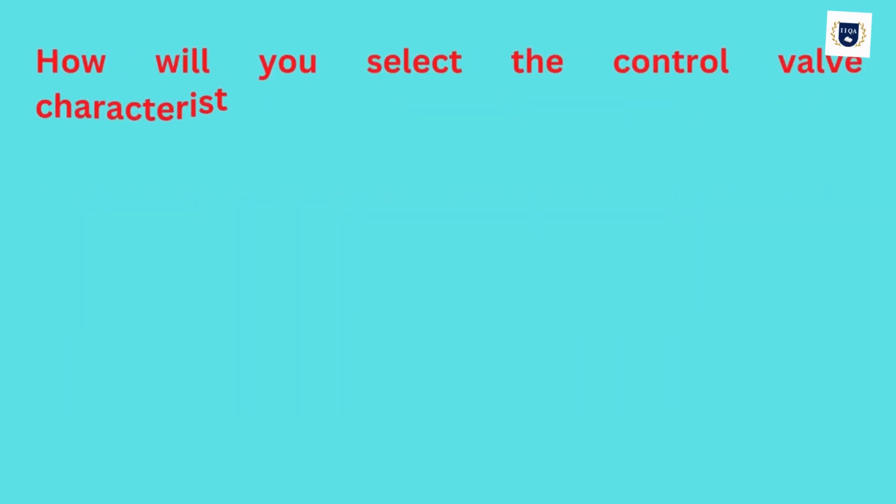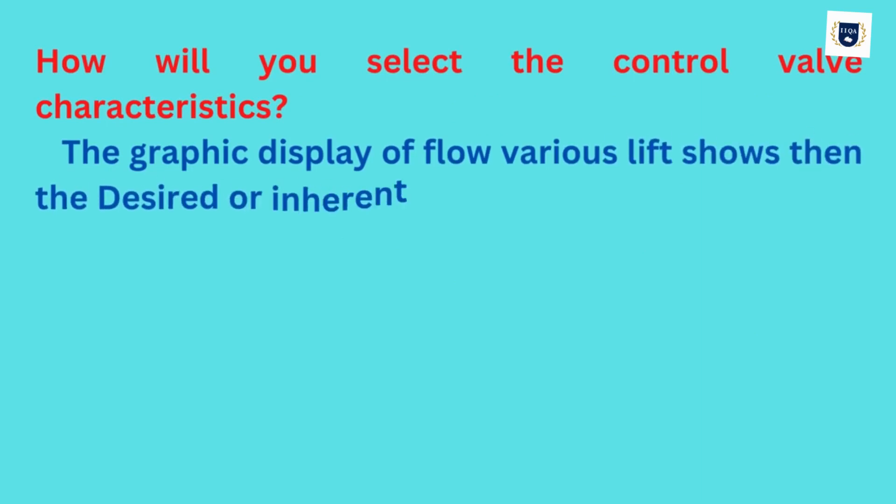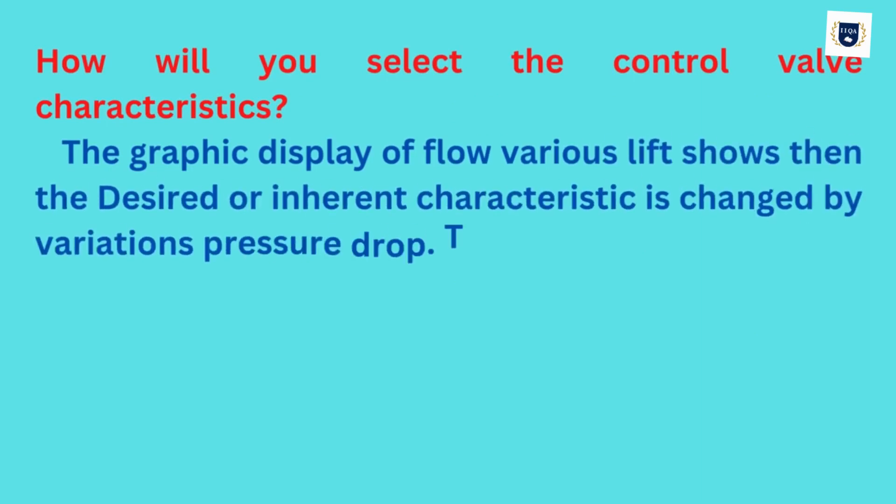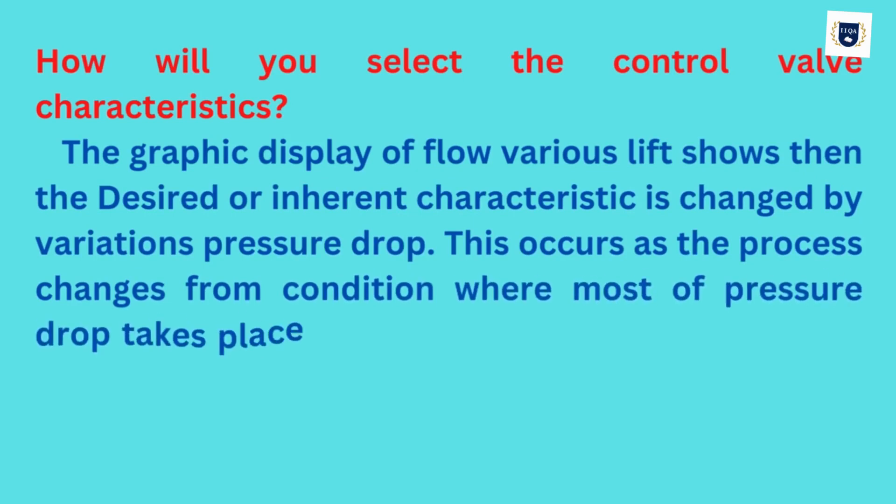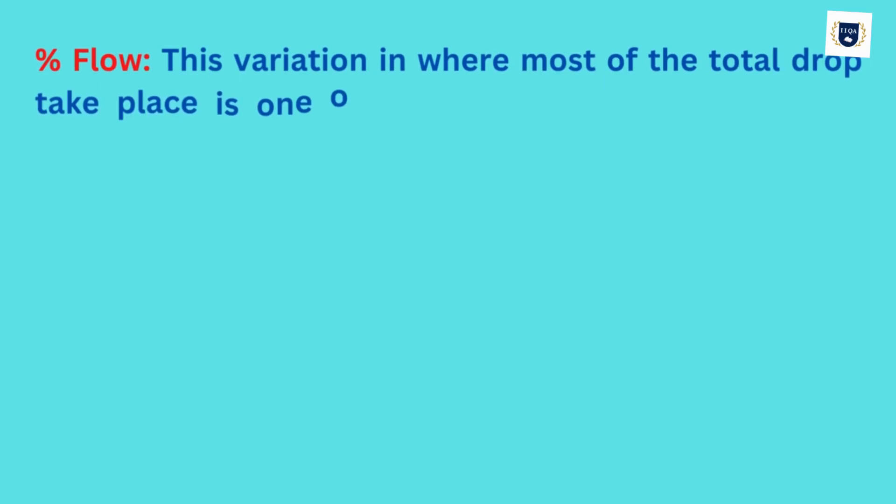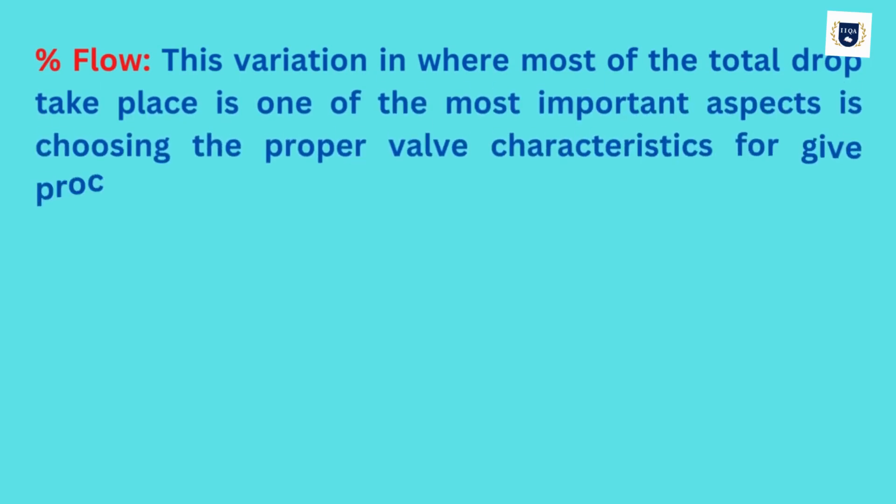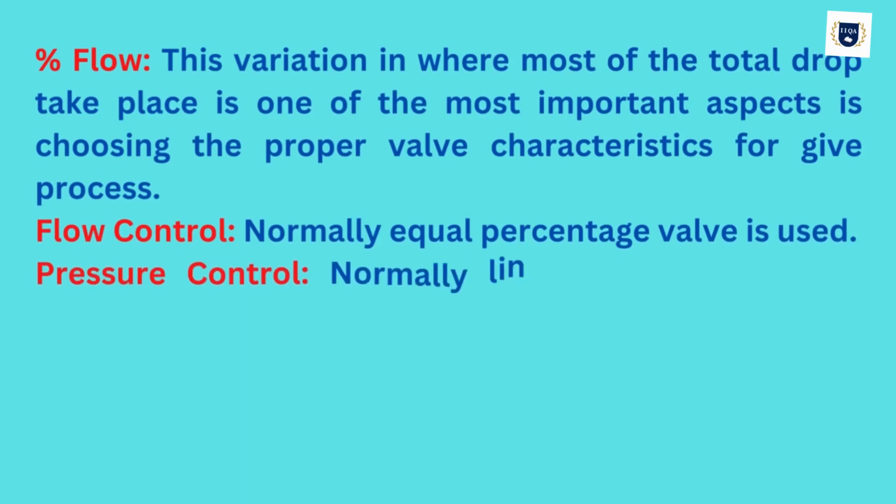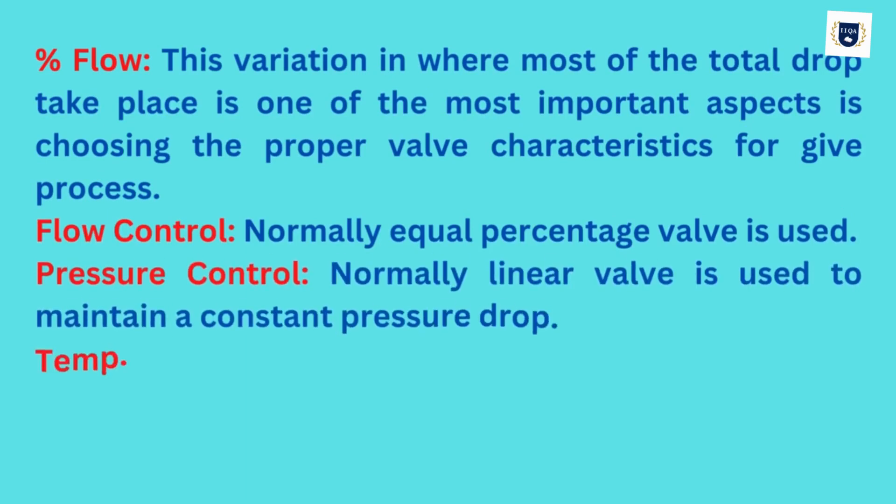How will you select the control valve characteristics? The graphic display of flow versus lift shows that the desired or inherent characteristic is changed by variations in pressure drop. This occurs as the process changes from a condition where most of the pressure drop takes place at the control valve to a condition where most of the pressure drop is generally distributed through the rest of the system. This variation in where most of the total drop takes place is one of the most important aspects in choosing the proper valve characteristics for a given process.